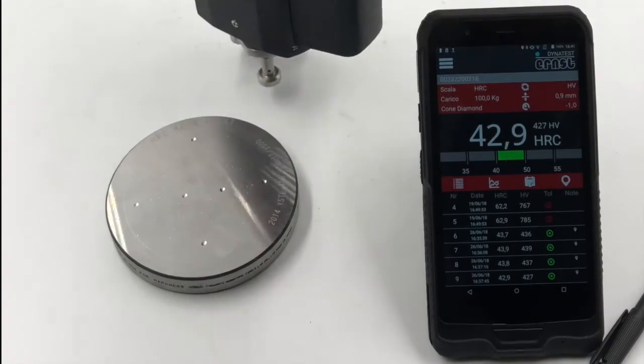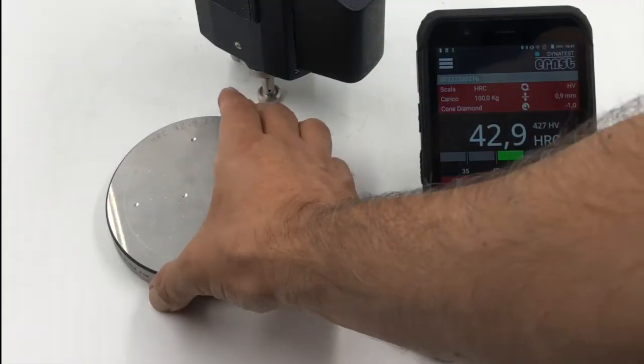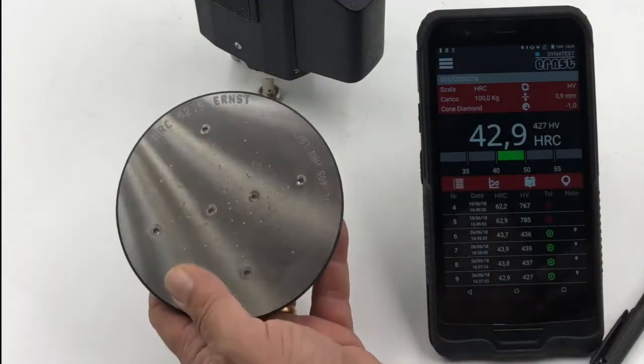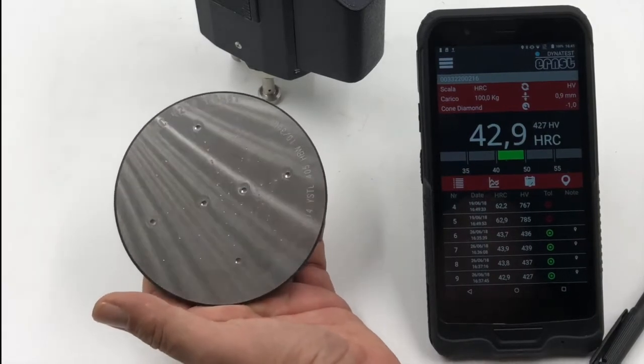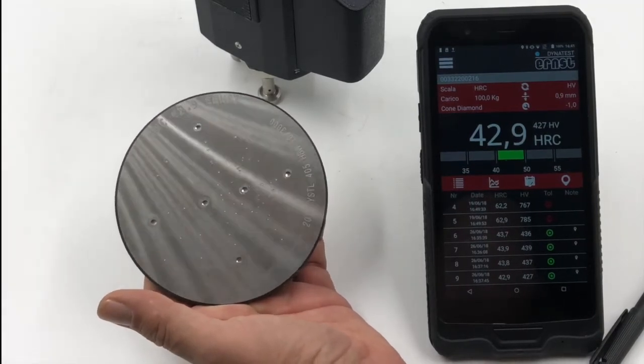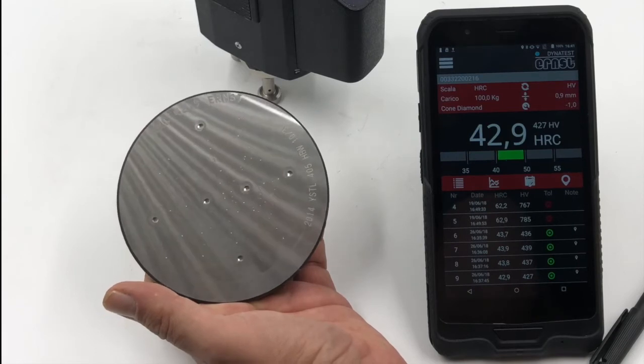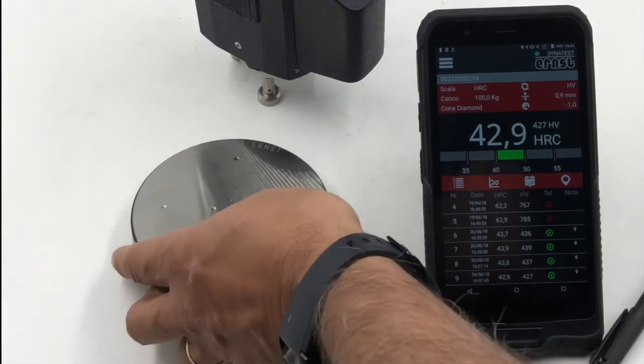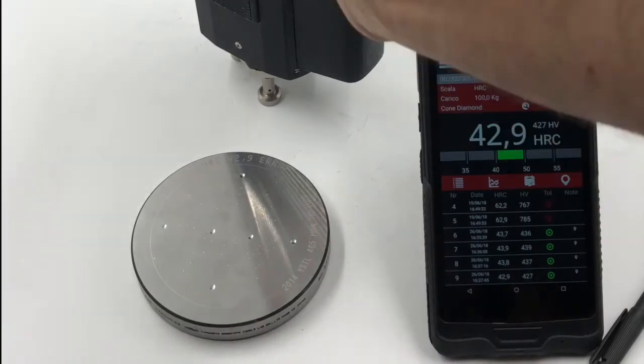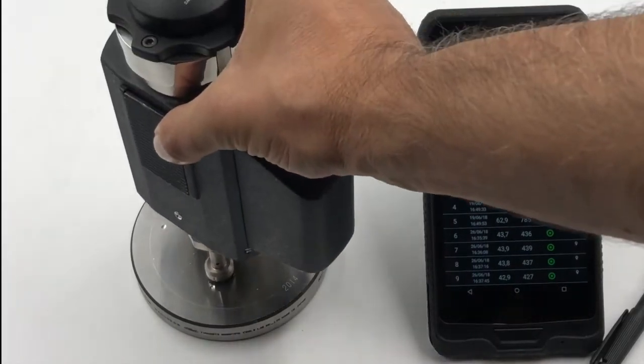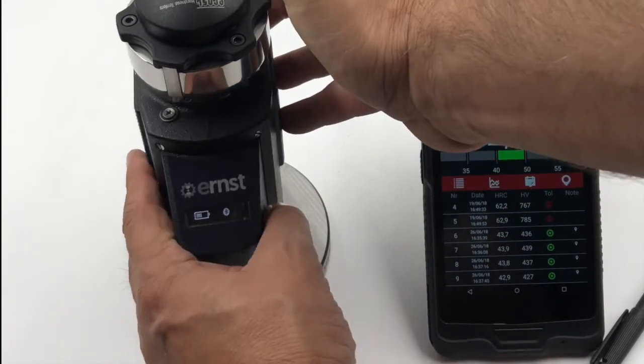Now, with the e-dynatest, we probed here a calibration standard. Calibration standard written 42.9 HRC. Let's see if we are able to achieve the same value.